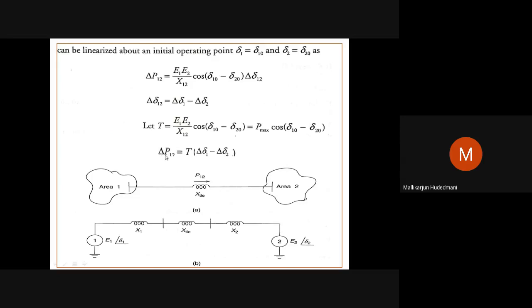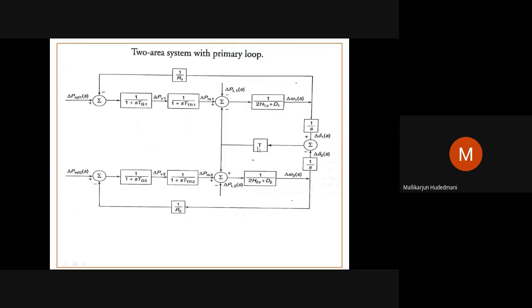What is this T? T is what I have discussed here. Delta P12, the actual exchange of power among the areas, is delta delta 1 after integration of the angular frequency of that particular area 1, angular frequency of area 2, take the difference of those two in the summer block and multiply with the T, which is P max cos delta 10 minus the initial power exchange. So when I operate, that is a T block here. Delta delta 1 minus delta delta 2 into T. This comes forward, and let's see how it is interconnected.